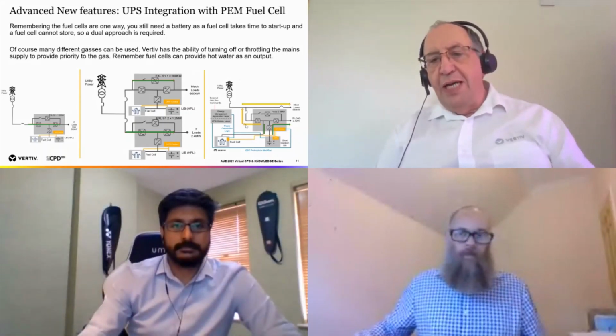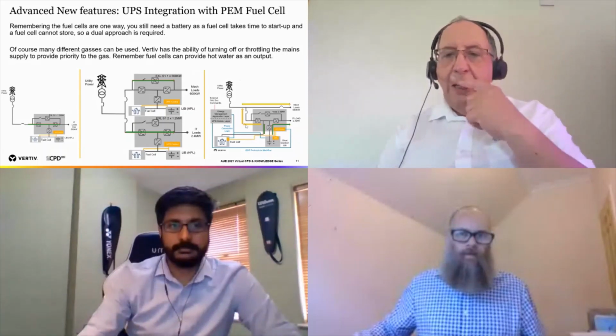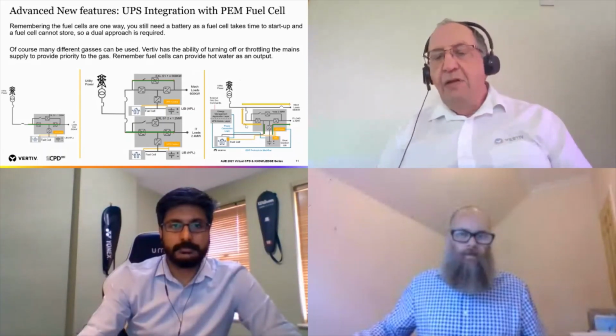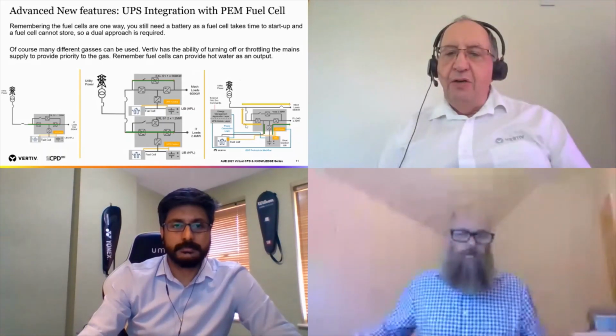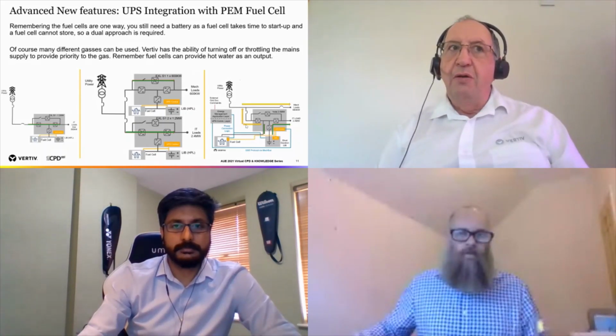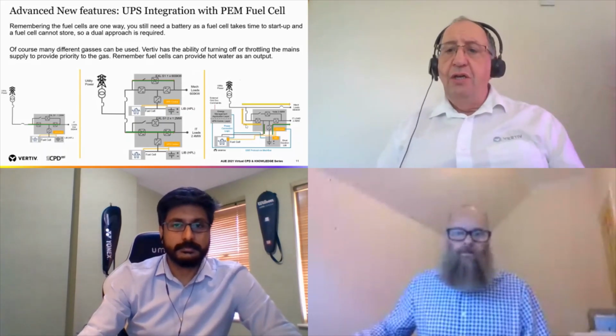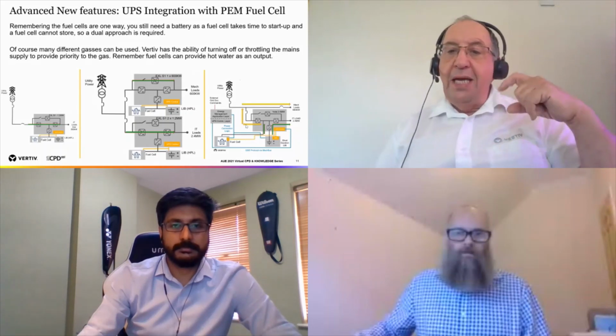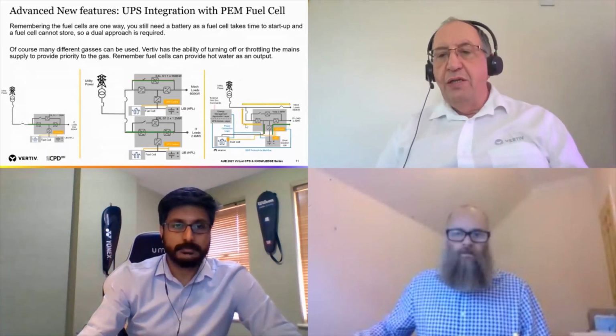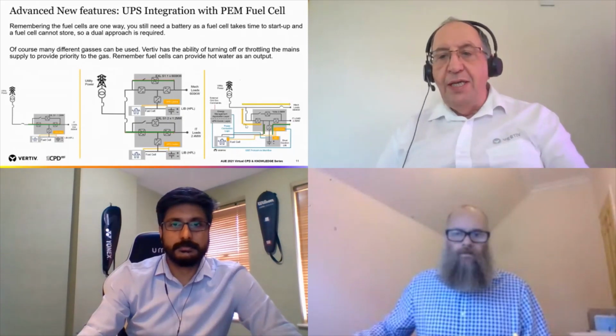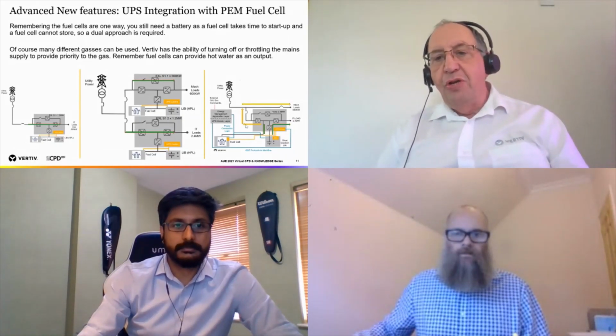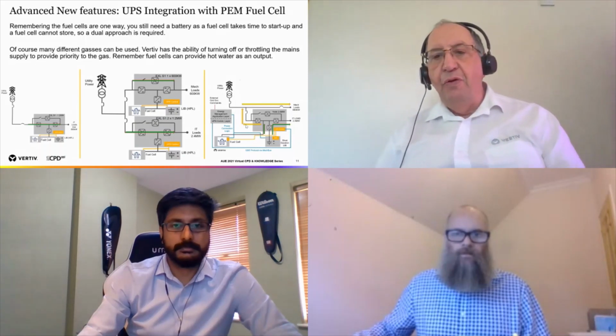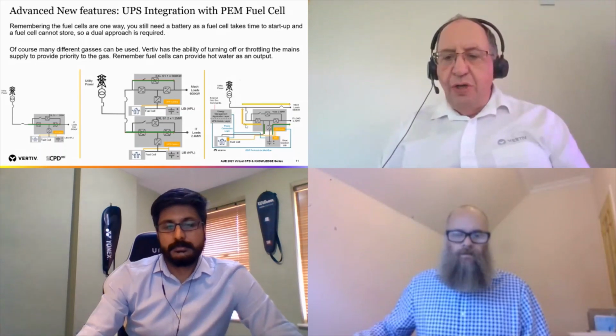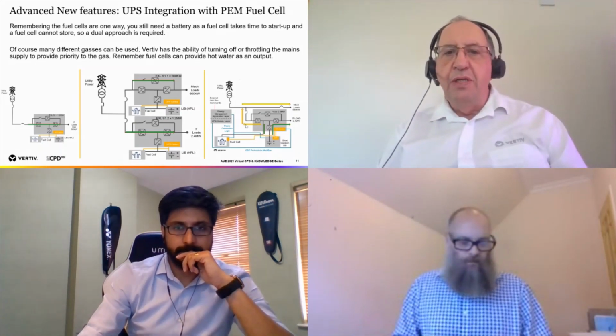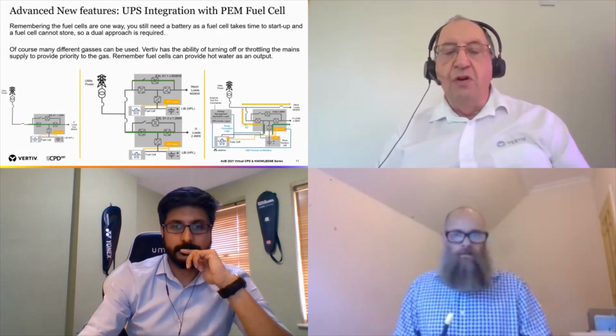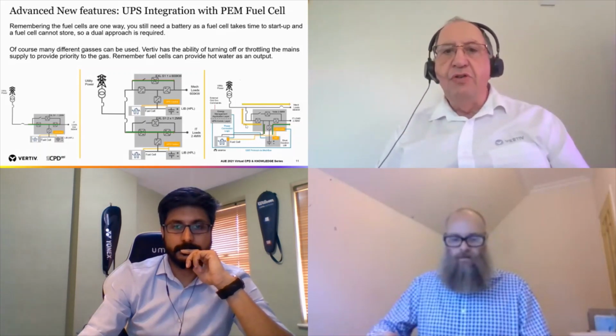And then the right-hand diagram is actually using the fuel cell to backfeed the grid and to keep the UPS alive. So we've got the mechanical loads being fed directly from the fuel cell because there's a short break, so we can turn the mechanical loads off and then put them back on again once the fuel cell is up and running. But at the same time, the IT load is running on the lithium ion battery until yet again it gets the feed from the fuel cell. So I think you can understand that there's quite a lot of interest in that and work going on at this moment in time. And I understand that Vertiv have got a test rig if you guys are interested in seeing that.